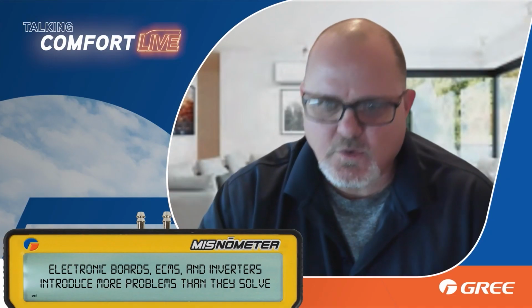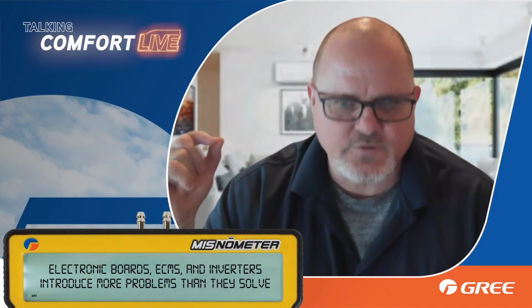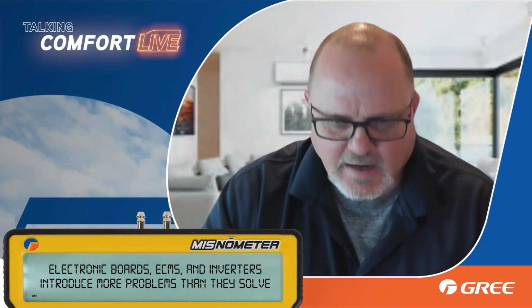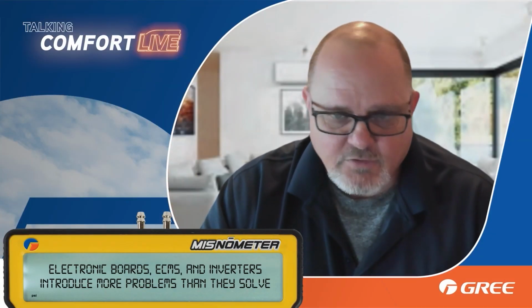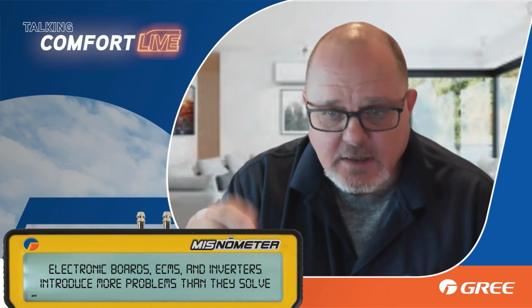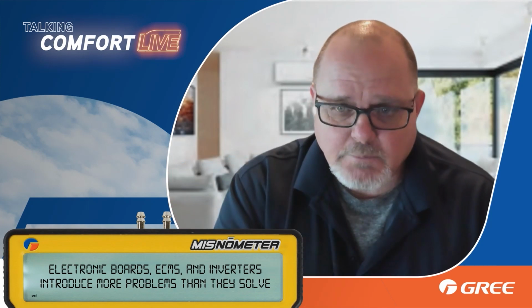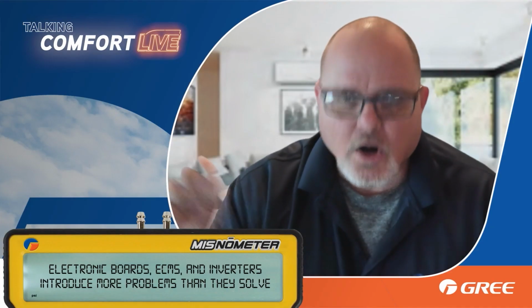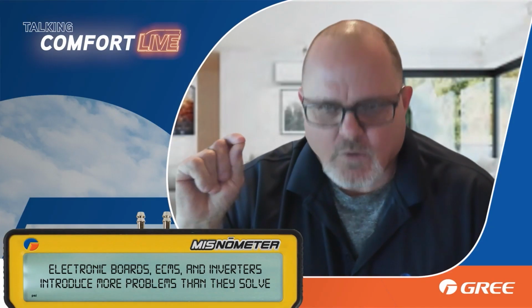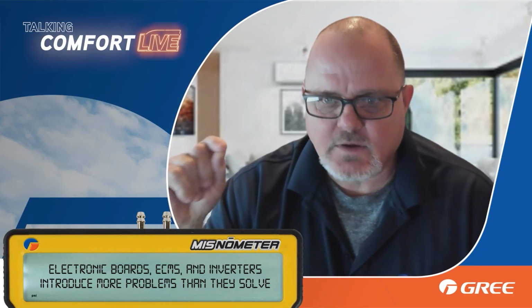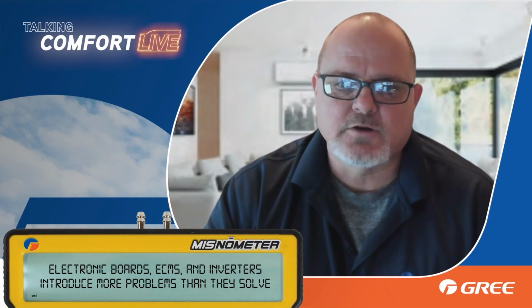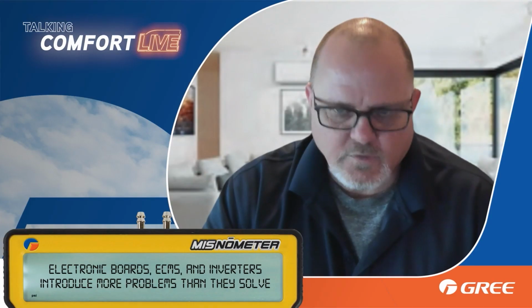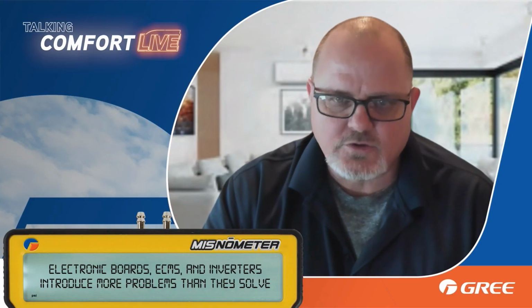That's essentially what happened. Now, if you buy any new furnace, any new air handler, doesn't matter who the manufacturer is, you are not getting a blower with a capacitor anymore. You're getting an ECM fan. It's inevitable. I believe that PSC compressors that are in standard equipment today are going to go away. What's going to happen is you're going to have electronically commutated motors in the compressors or inverter-driven compressors. That's where the technology is going.